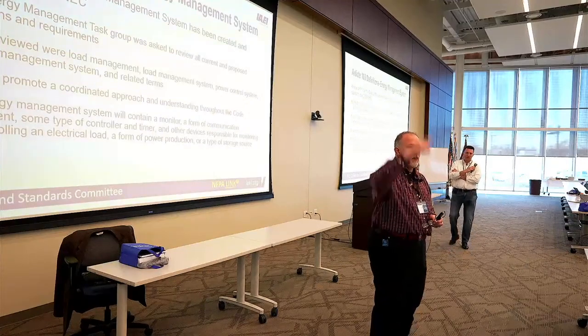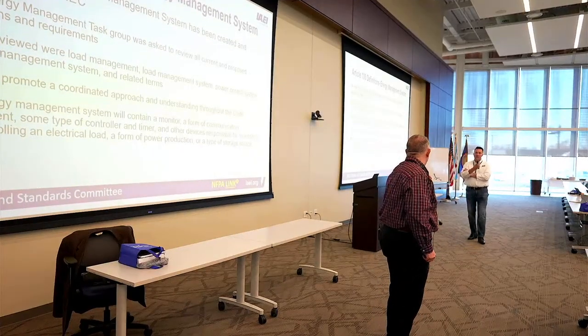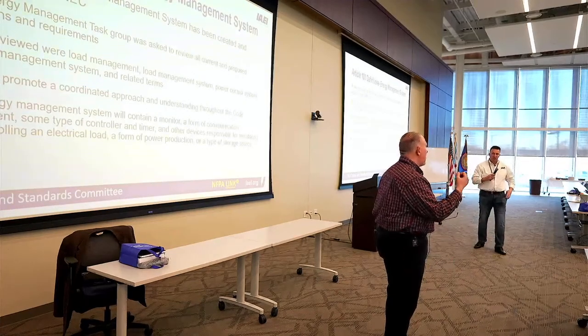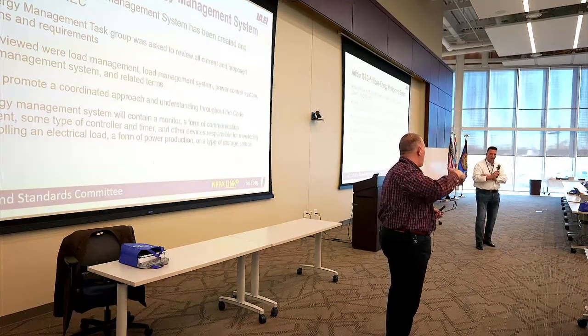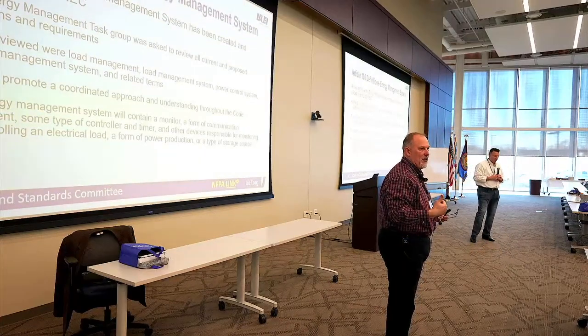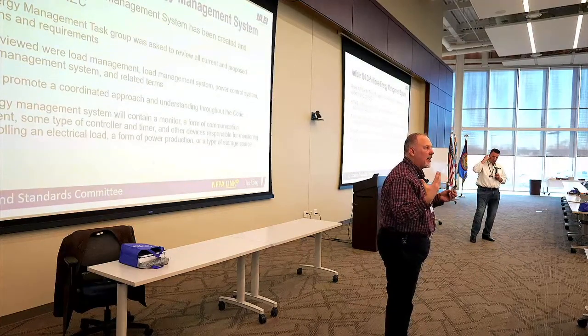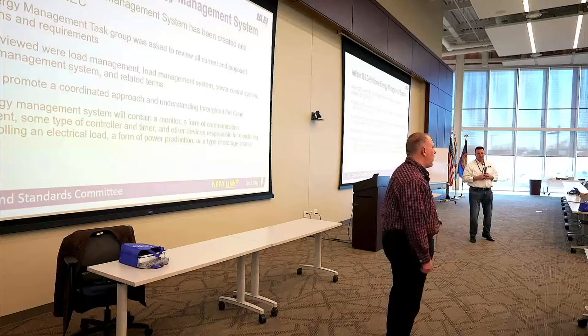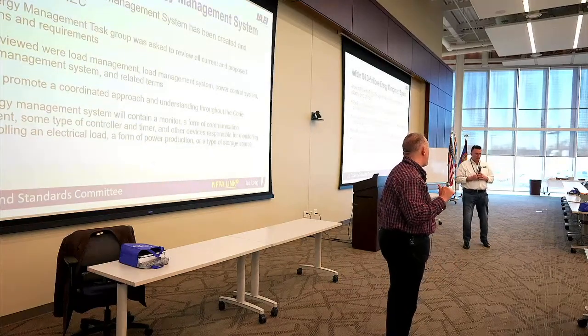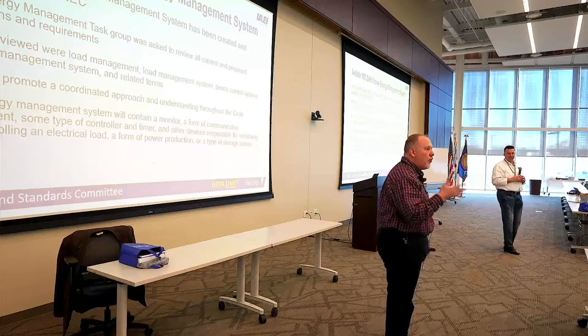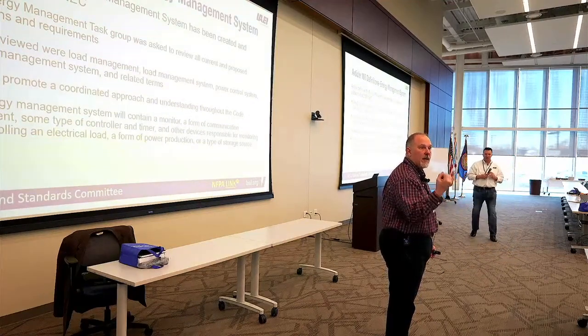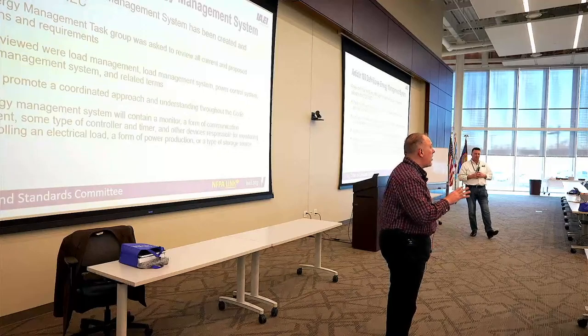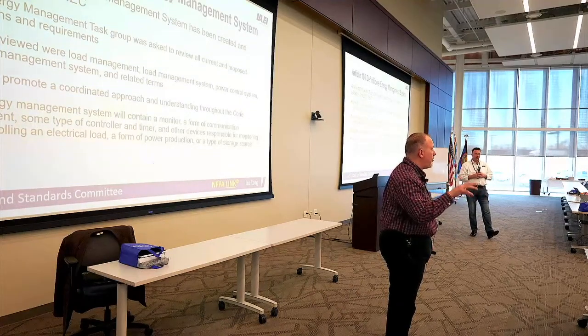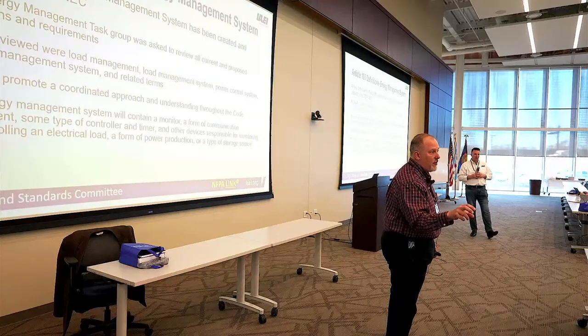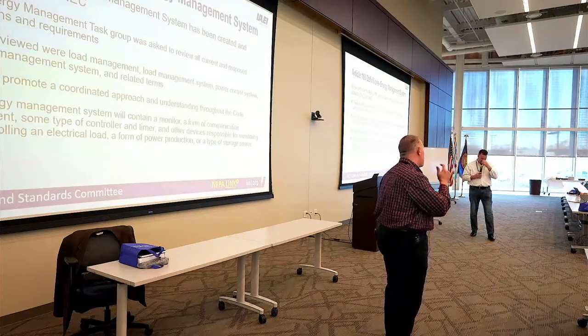If your energy management system relies on a cloud, like EV chargers - EV charging equipment is relying on, in some cases, the cloud for set points on how much current they're going to draw. So now they're into this energy management world using a cloud-based system. What happens if the cloud goes away? What happens if I forget to turn it on, or my brain goes dead, which for me happens often, but in the equipment it may happen. And if it does, what's the default values, and will I now overload my service, my conductors, my equipment? So you're going to see a lot of changes moving forward to address the use of energy management systems when we're relying on that to size services, feeders, and other distribution equipment.